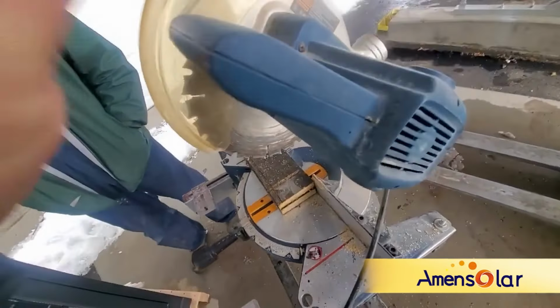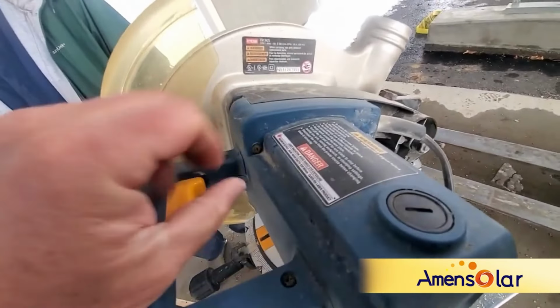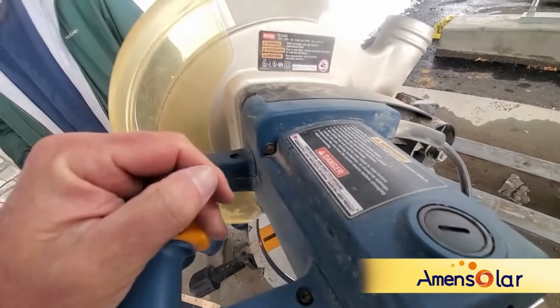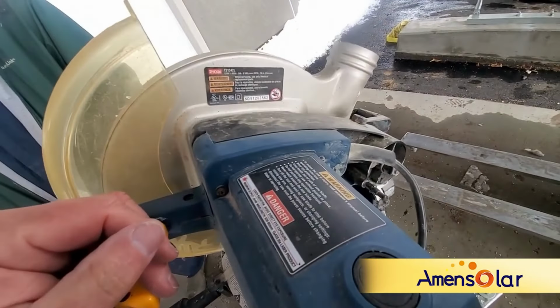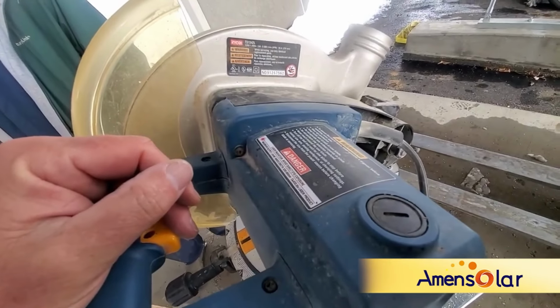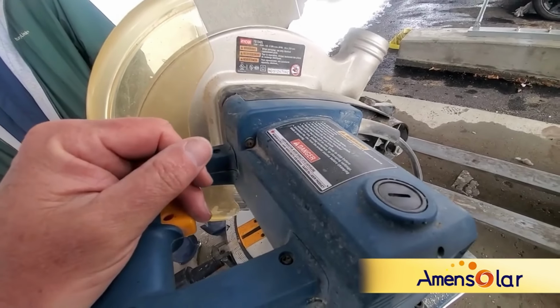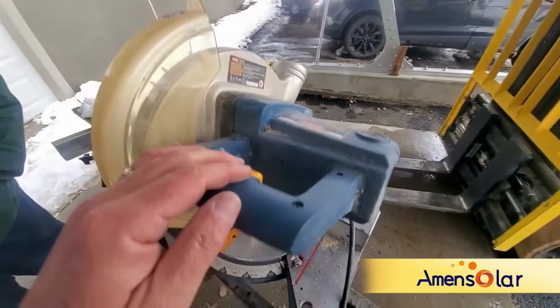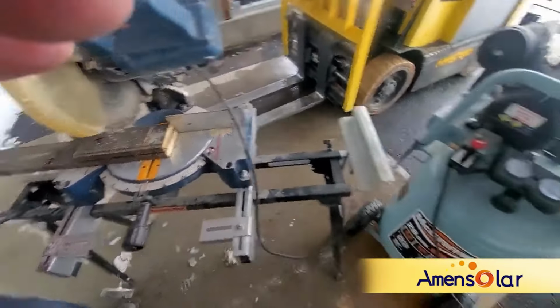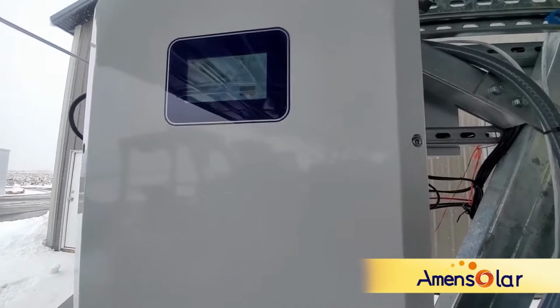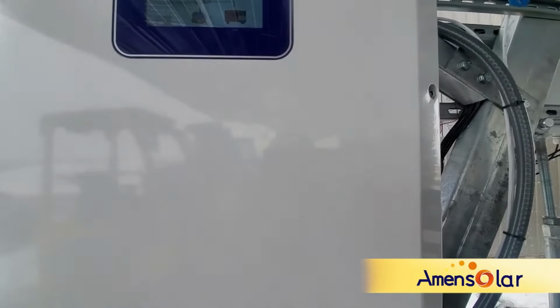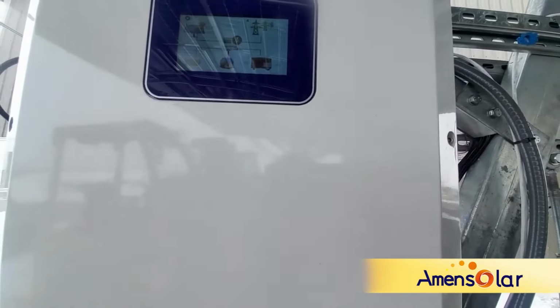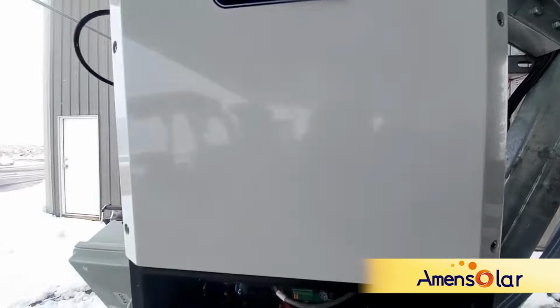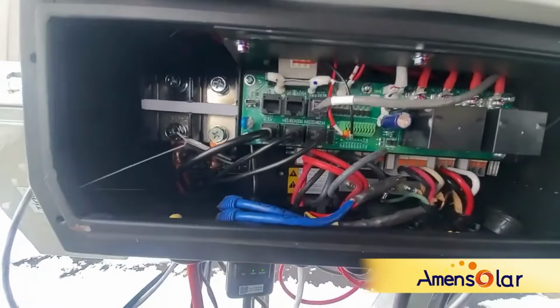And here we have a chop saw. We're actually going to start this guy off with a locked rotor, and show you that we just basically see if the inverter handles it. Now this is a 120/240 volt inverter, so it's 5 kilowatts per phase. We're just going to be testing it as max as we can on one single phase and then on 2 phases. And this is what it looks like inside.